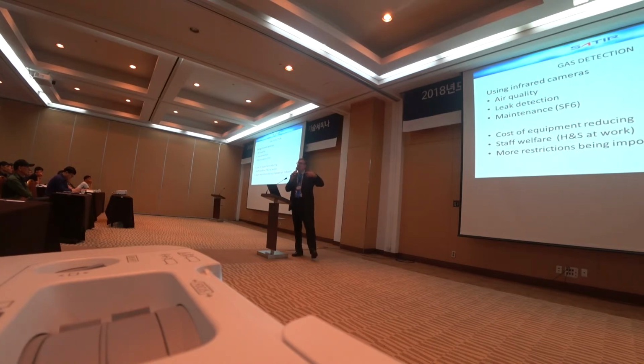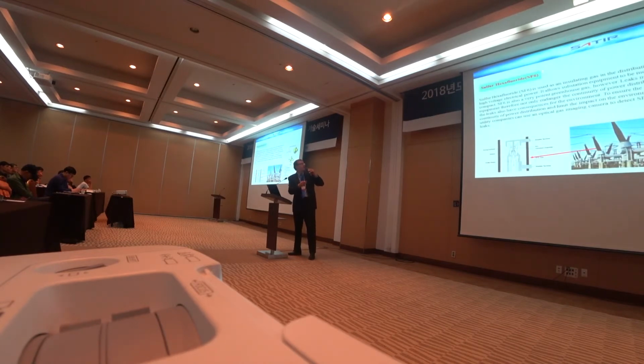What's happening now? Most people use thermal cameras for electrical and mechanical. We're now using it for looking for air impurities and escape of gases. So again, we're looking for SF6 or benzene. They're some of the chemicals for which we'll be looking for an escape of gas. I'm not going to go too much into the SF6, but again, we're normally looking for problems around these areas where the gas is escaping.